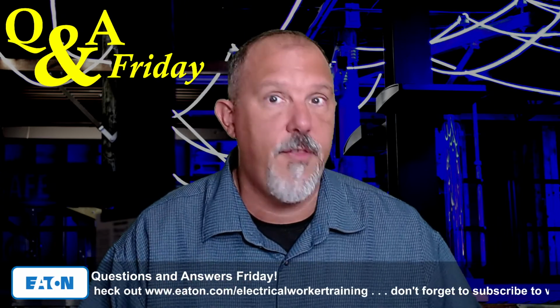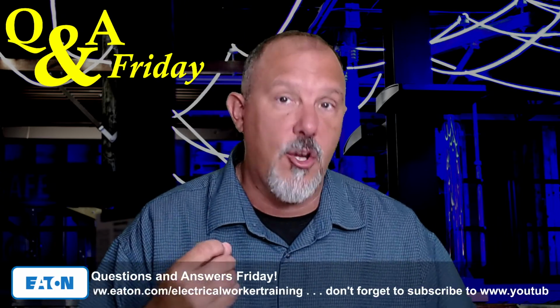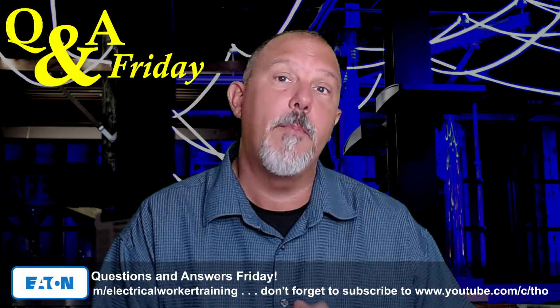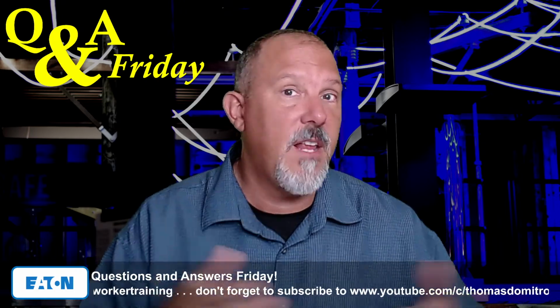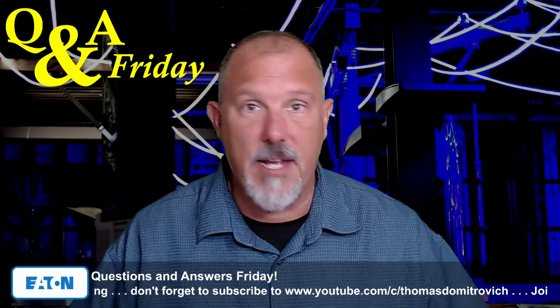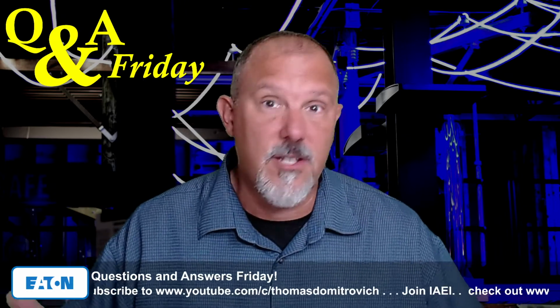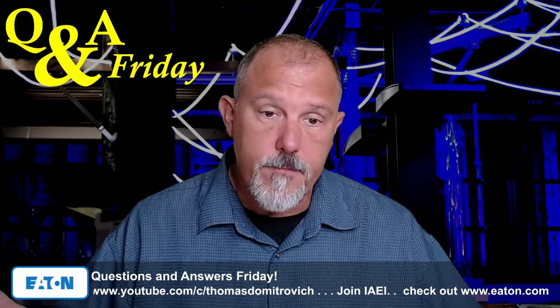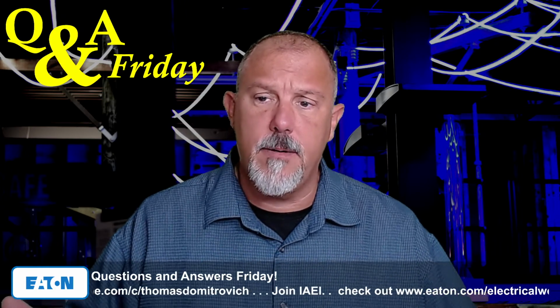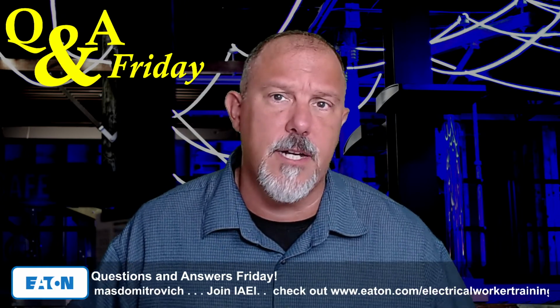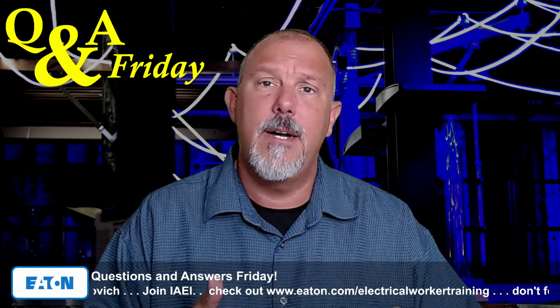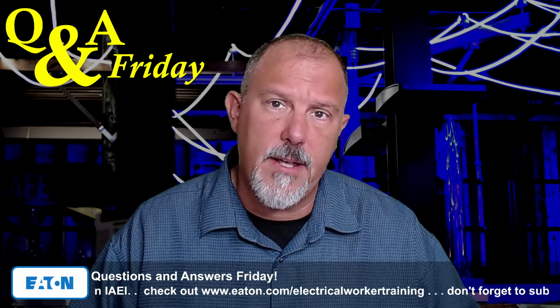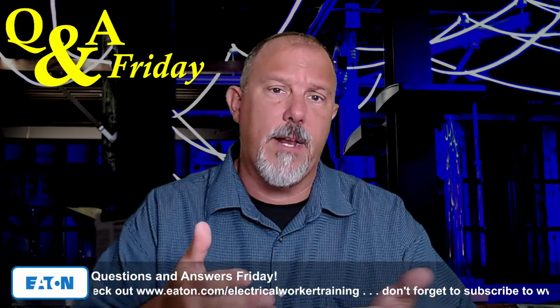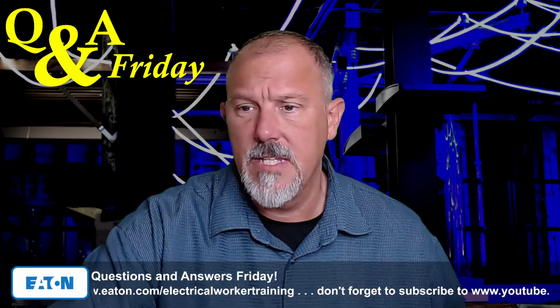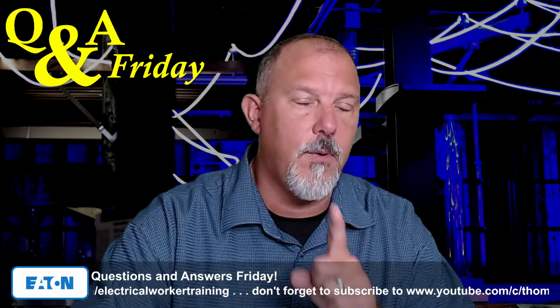I would agree that pulling a solid bare equipment grounding conductor is probably more reliable. But if I was a raceway manufacturer, if I manufactured those flex or whatnot that was used, I would say, hey, that's just as reliable. And I could accidentally pull out that equipment grounding conductor, just like I could accidentally destroy my ground fault current path when I damage my raceway. So in any case, it's there because it's there.